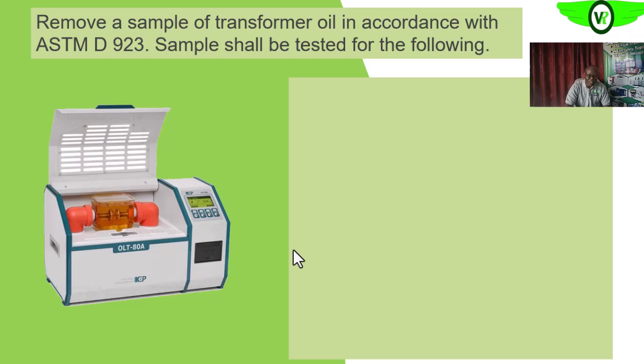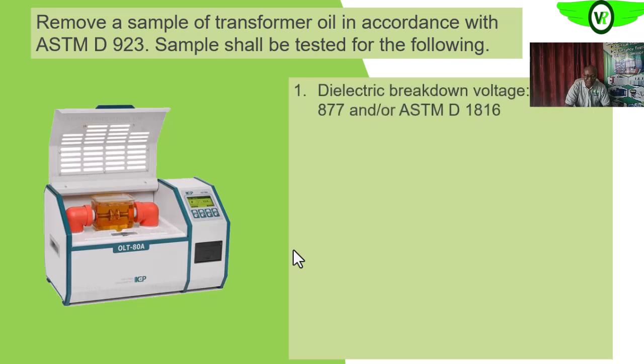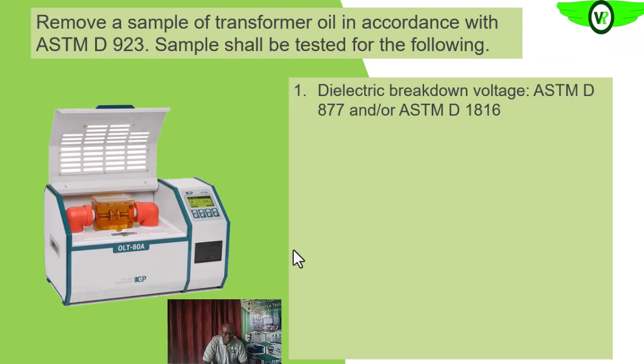So we'll take a sample of the oil from the transformer, and then we can test the sample that we collected for the breakdown of dielectric strength. The dielectric strength of the oil is the voltage at which it starts conducting between these two electrodes, and it depends on the spacing of the electrodes. So you adjust the spacing, and we should get a result that is acceptable at the end of the day.